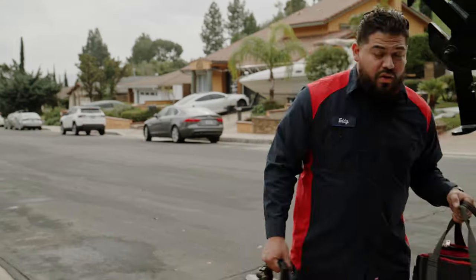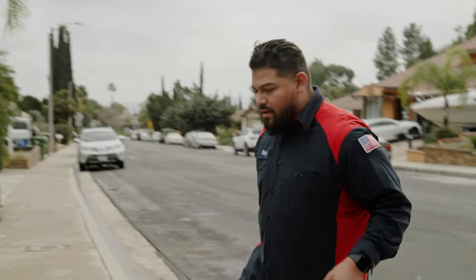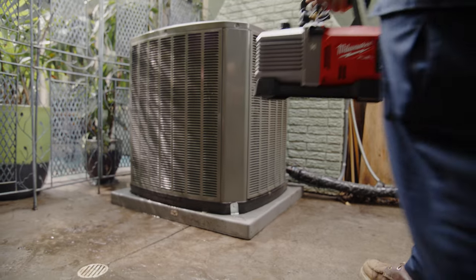We got a no AC call. Diagnosed the problem, figured out it was the filter dryer. So we're gonna change it, get it all pumped down, and use the Milwaukee vacuum pump.